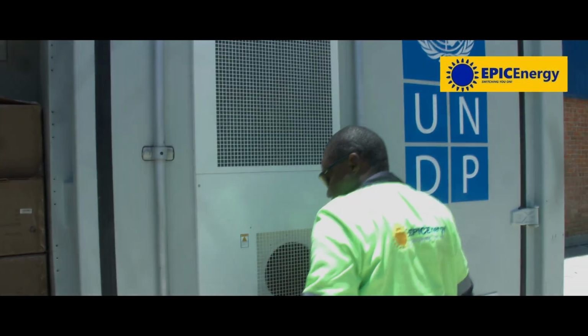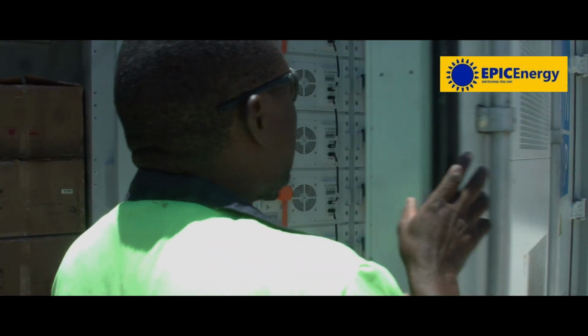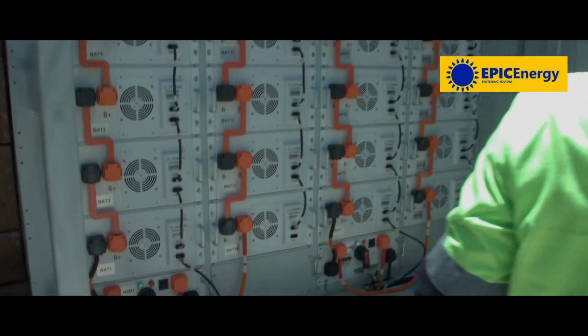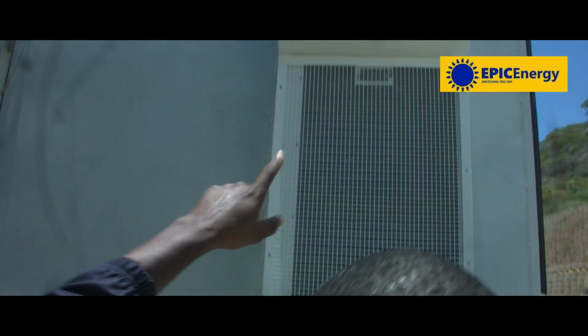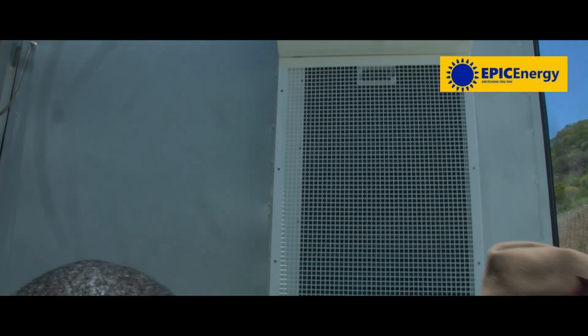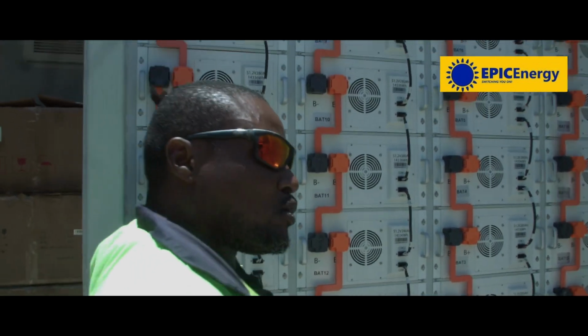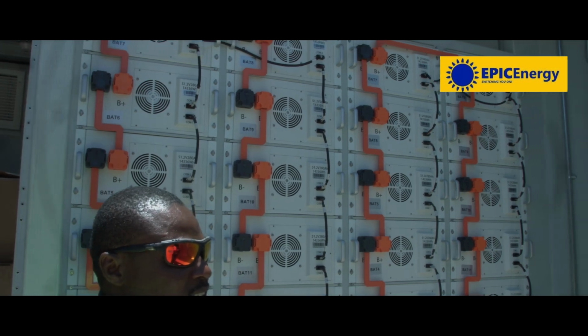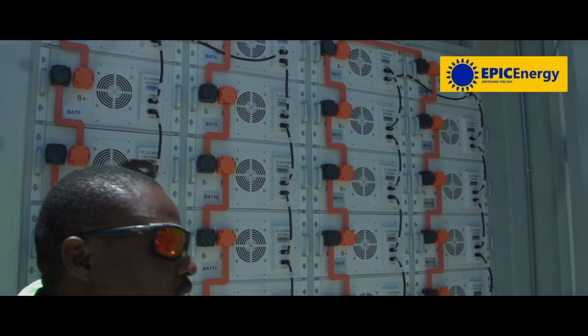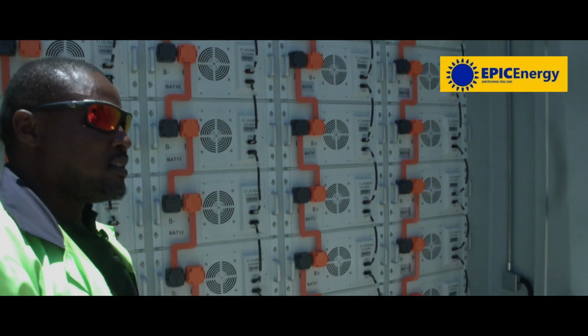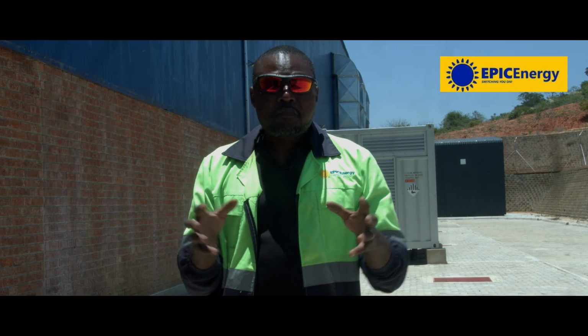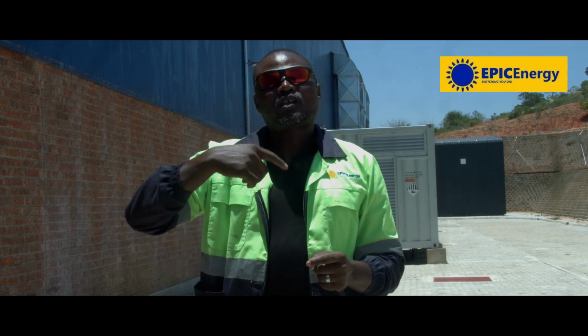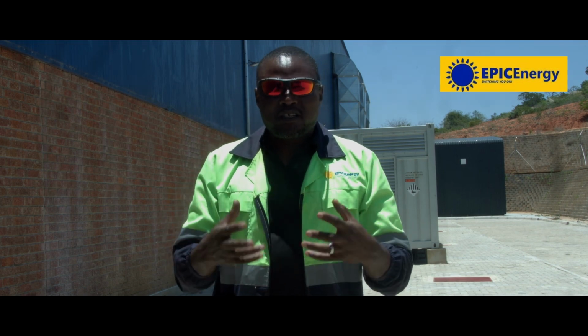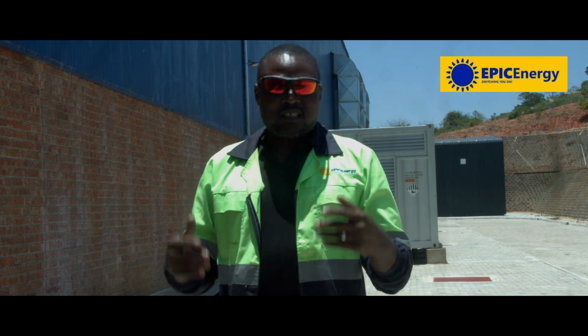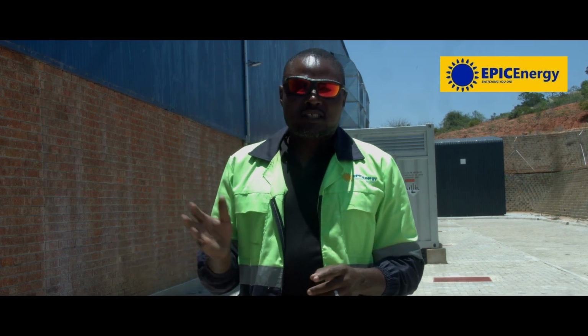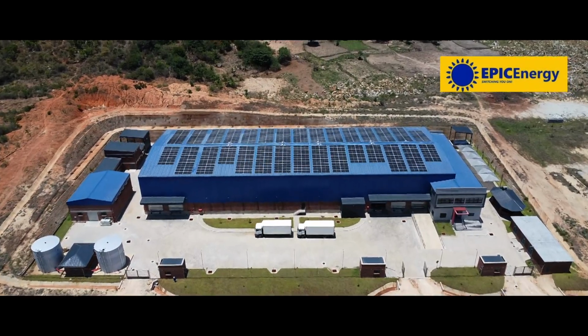Then from there, once it goes into the inverter, our system has a battery bank. We have 4 clusters of the battery bank, which need to be switched on and switched off chronologically when you want to set up the system. So here's a kicker. Because of the fire suppression system that is linked to the entire unit, if the fire suppression is not operational, the system is not going to kick in. So when you're setting it up, there is a UPS inside which makes sure the fire suppression is constantly and continuously operational for the system to operate. Otherwise, the system is down. That's a protection mechanism that is installed with this particular system right here in Mutare.